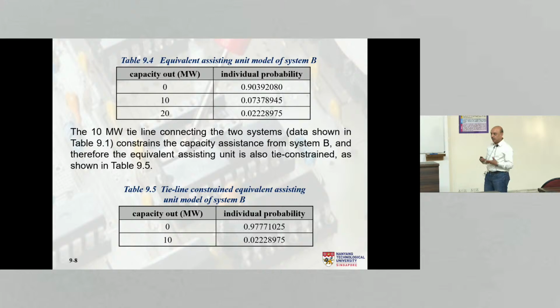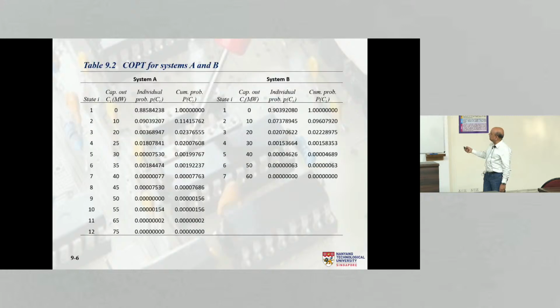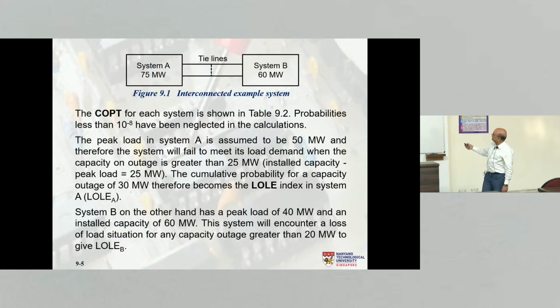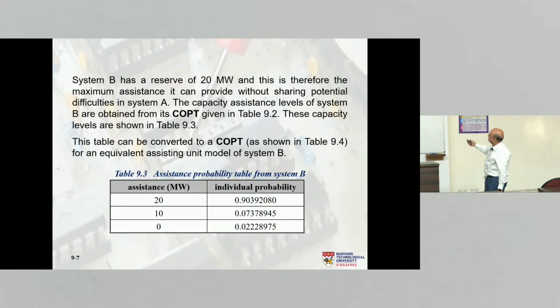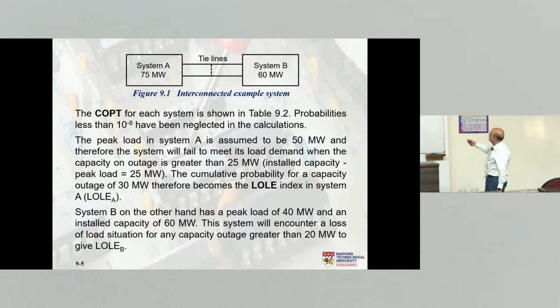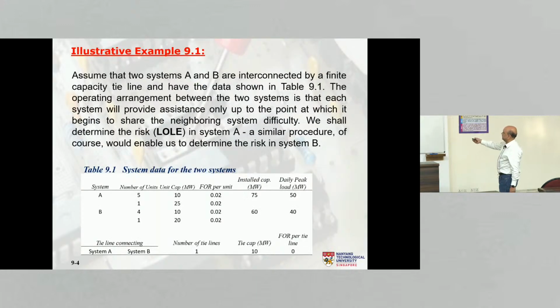What I'm saying now is that because the capacity of the tie line is only 10 megawatt, we mentioned that earlier, right? The capacity of the tie line is, what did I say? Let me look at it. Oh, somewhere I must have. Is it here? No, previous one. Yeah, here. The tie line capacity is only 10 megawatt. And of course, it doesn't fail, which is not realistic, but doesn't fail, okay?